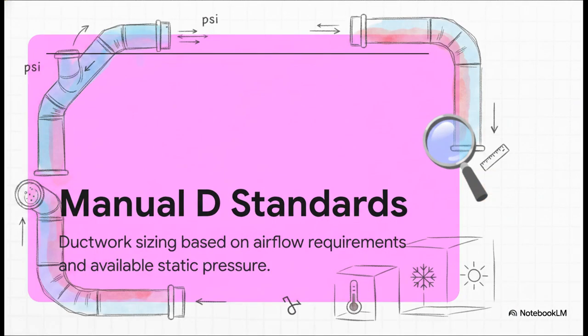Additionally, you want a contractor who utilizes Manual D standards, detailed calculations specifically for ductwork sizing. They look at airflow requirements, friction rates, and available static pressure. Using Manual D ensures that conditioned air actually reaches every single room properly. It prevents those incredibly frustrating temperature imbalances, like when your downstairs living room is freezing cold but your upstairs master bedroom is an absolute sauna.